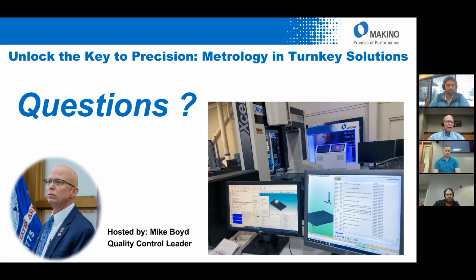We've seen differences in gauges used between inspections here and at the customer's facility, and sometimes a greater difference, but as long as the values are stable, we can certainly dial into the customer gauge when the turnkey gets delivered.